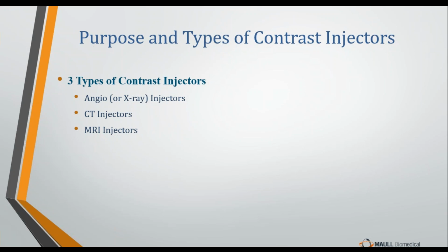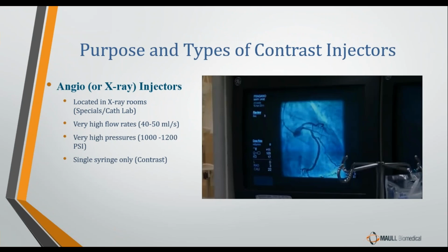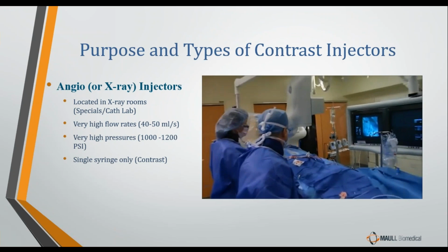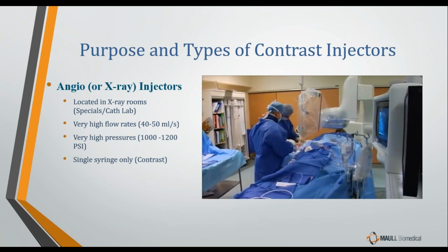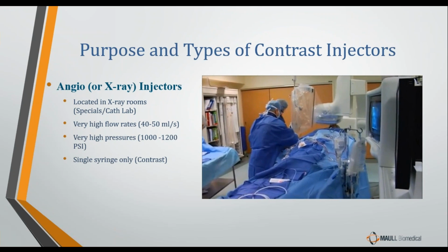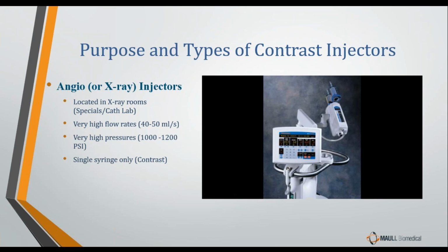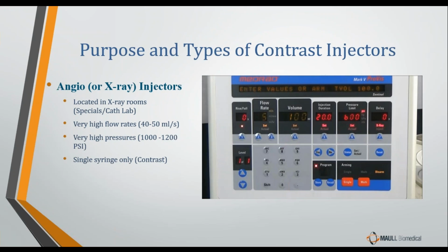Now, I mentioned earlier that basically you've seen one, you've seen them all, and that is true for the most part. 90 to 95% of all contrast injectors are identical to each other. But there are subtle differences that do make an angio injector different from a CT injector and slightly different from an MRI injector. And we're going to talk about some of those subtle differences right now. So first off, let's talk about the angio, or the X-ray injectors. Now, this particular injector is going to be located in your specials, your cath lab. This is going to be in the room with the big giant C-arm in it, basically.